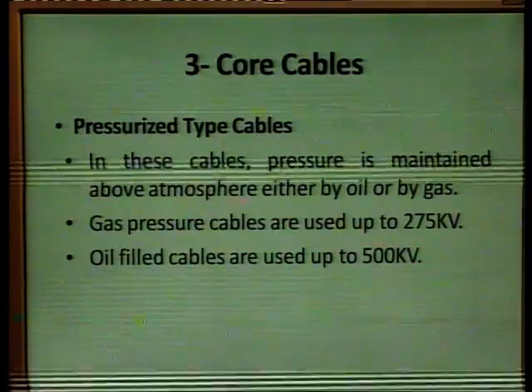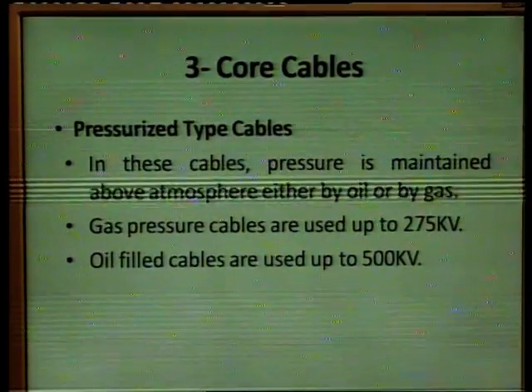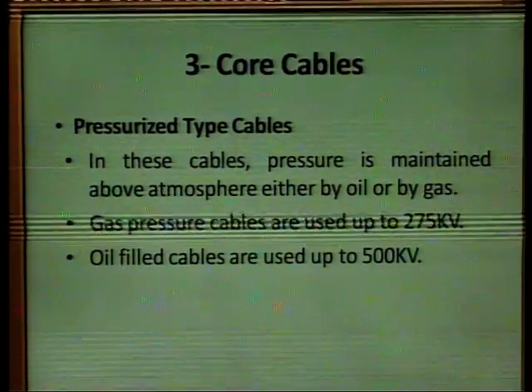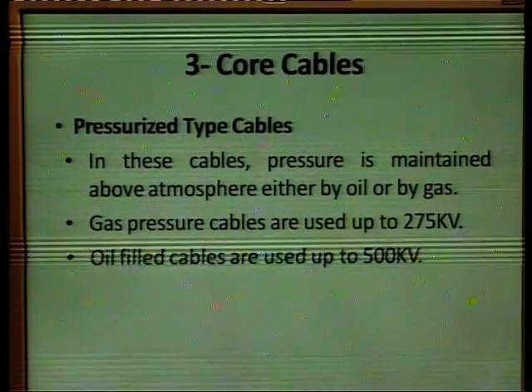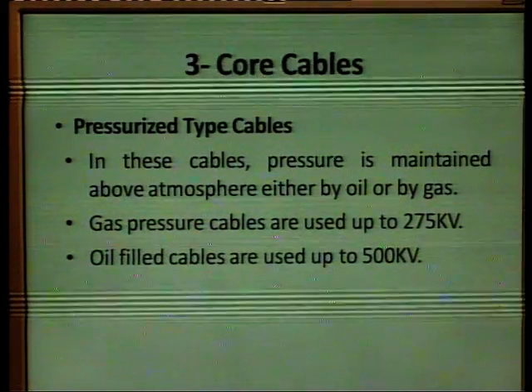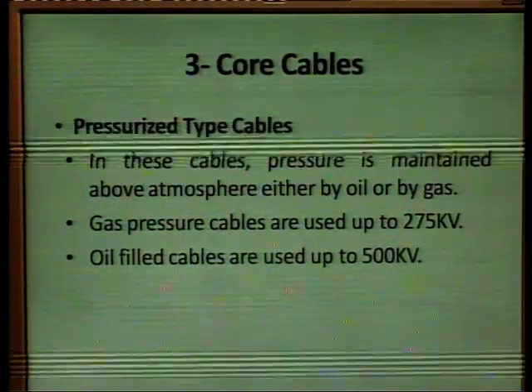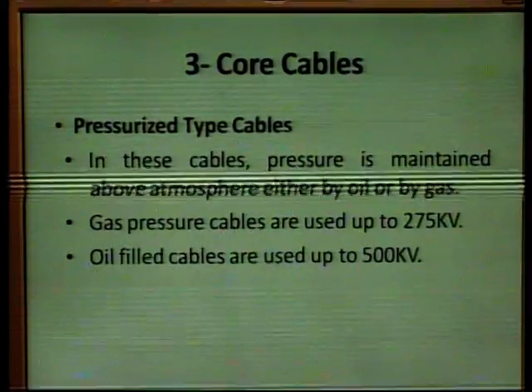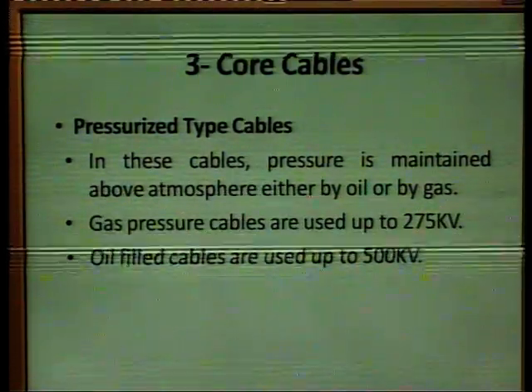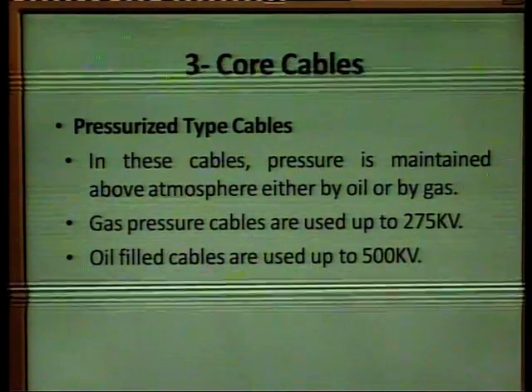In the next category we have the 3-core pressurized type cables. In these cables the pressure is maintained above the atmospheric level either by oil or by gas. The gas pressure cables are used up to 275 kilovolts, and the oil filled cables are used up to 500 kilovolts.